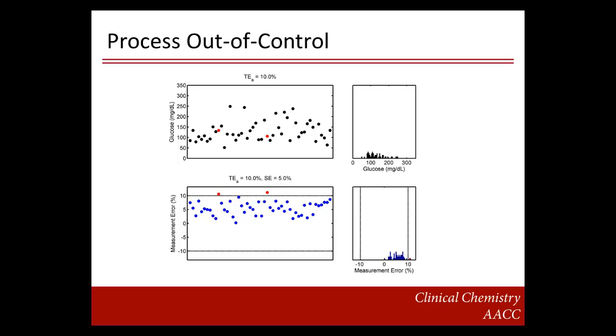Now let's say there is an out-of-control condition that caused a 5% upward shift in the process — a systematic error condition. The lab is unaware that the out-of-control condition exists. With an out-of-control condition, additional error is added. When you look at the glucose test results in the top left panel, you can't easily identify which results are unreliable. The red dot is an unreliable glucose test result. Plotting the measurement errors in the bottom left panel, you can see the errors shift up, and the glucose test results in red are outside the allowable total error limits, making those results unreliable.